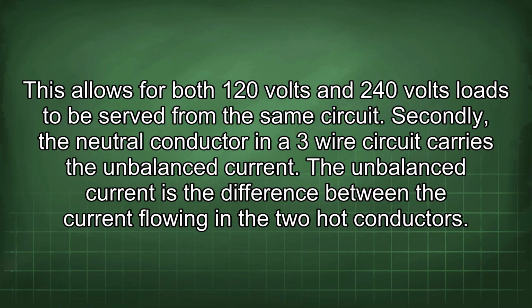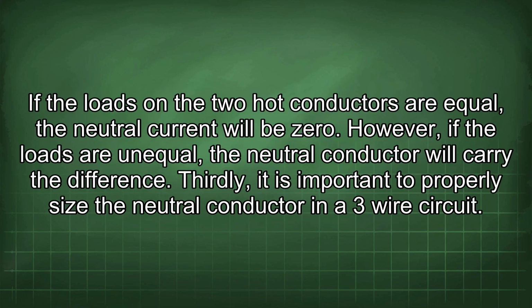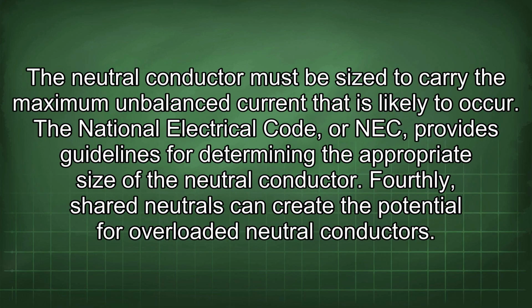Secondly, the neutral conductor in a three-wire circuit carries the unbalanced current. The unbalanced current is the difference between the current flowing in the two hot conductors. If the loads on the two hot conductors are equal, the neutral current will be zero. However, if the loads are unequal, the neutral conductor will carry the difference. Thirdly, it is important to properly size the neutral conductor in a three-wire circuit. The neutral conductor must be sized to carry the maximum unbalanced current that is likely to occur. The National Electrical Code, or NEC, provides guidelines for determining the appropriate size of the neutral conductor.